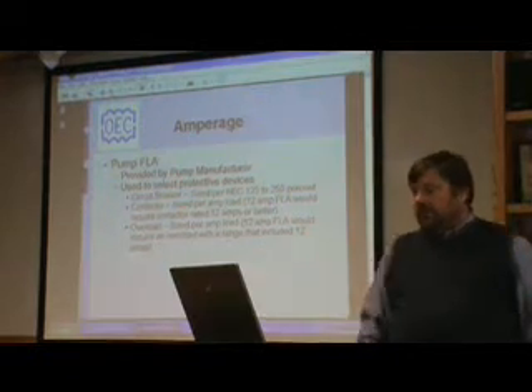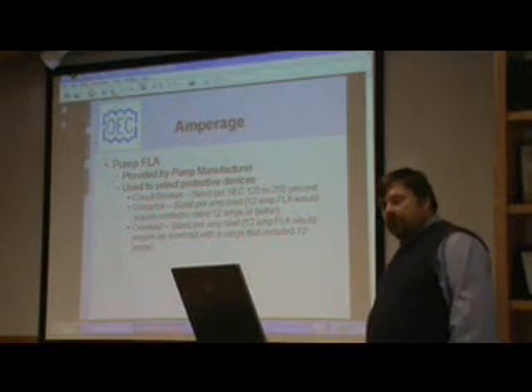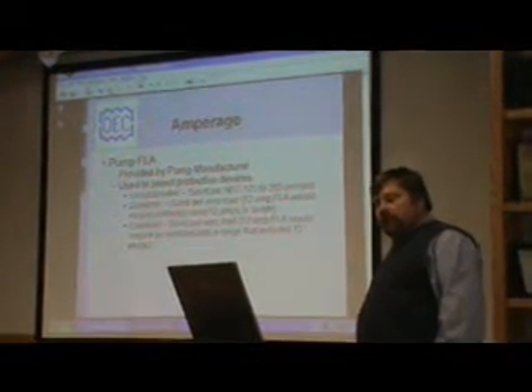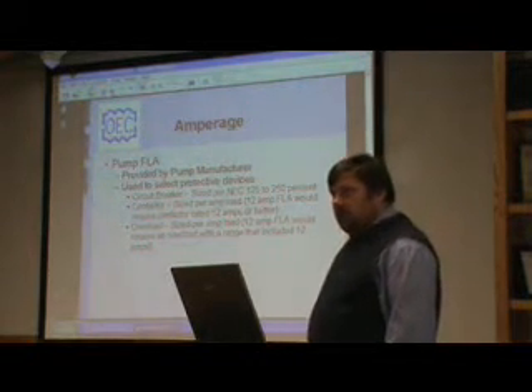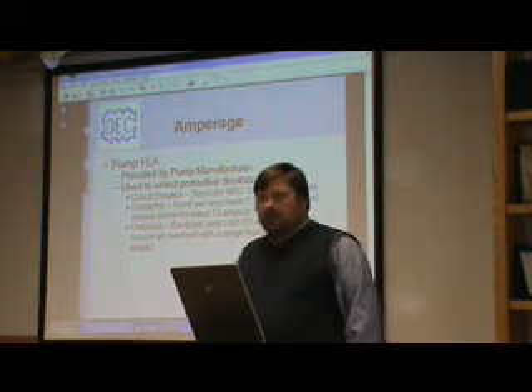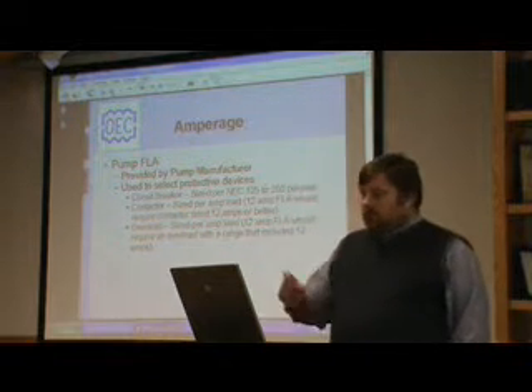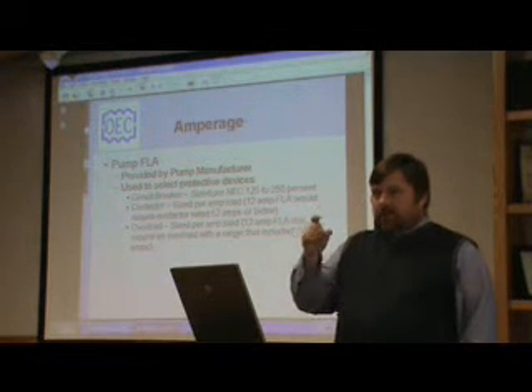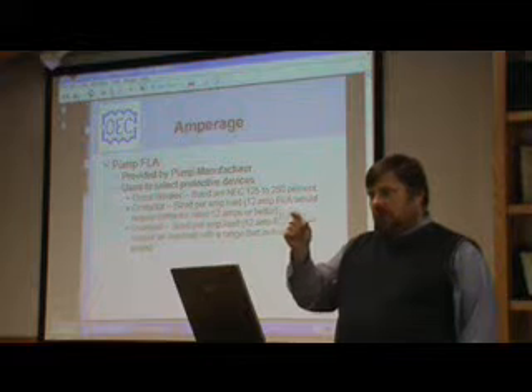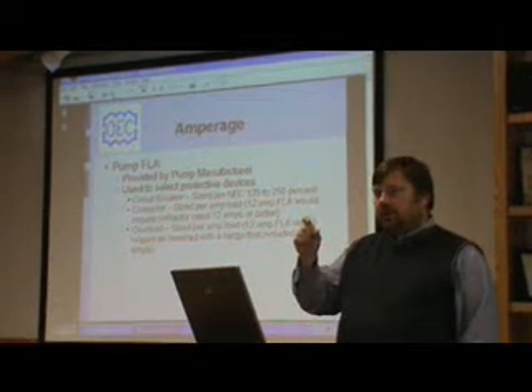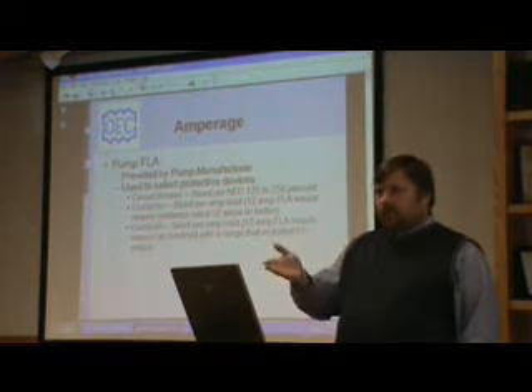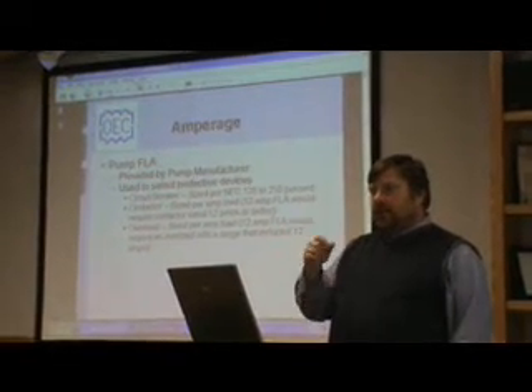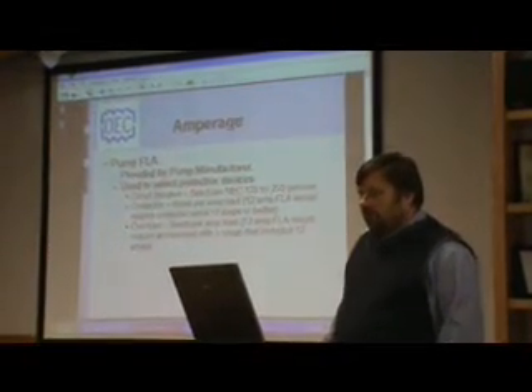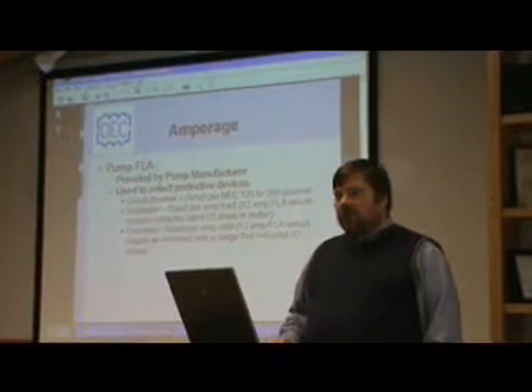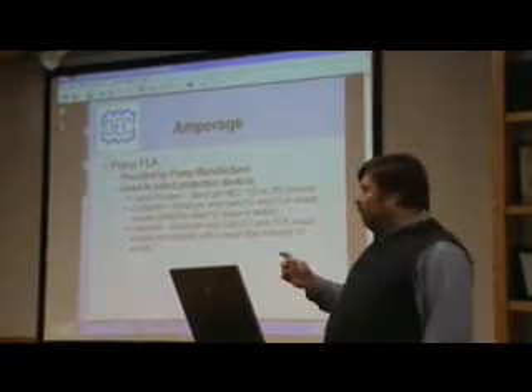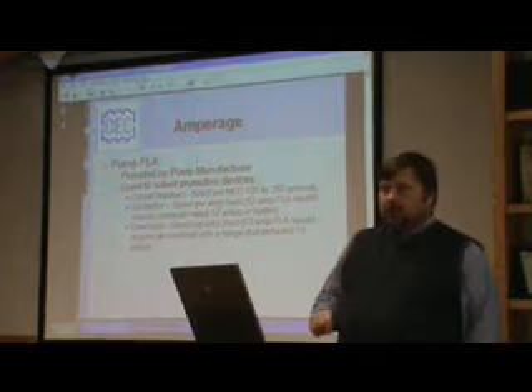Okay, the next device that we use that full load amps to size is the overload. And the overloads there again are selected based on that amperage. A lot of the older panels used to have a removable overload that had a heater you put inside there, and you looked at a chart and figured out what size that heater needed to be. Then if you changed your pump, or as the pump got older started to pull a little bit more amperage, you'd have to change that heater. A lot of the new overloads that we see used in panels have an adjustment range. So we want to make sure that that 12 full load amps fits within the adjusting range of that overload.